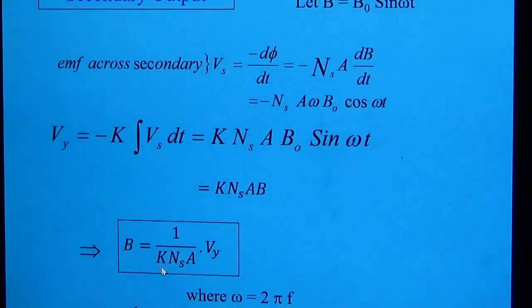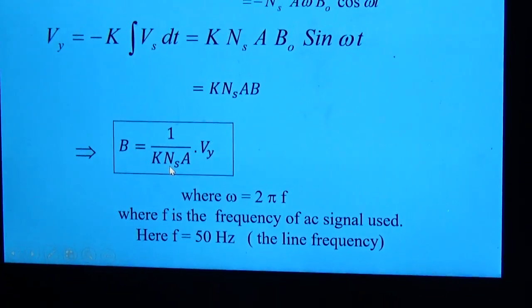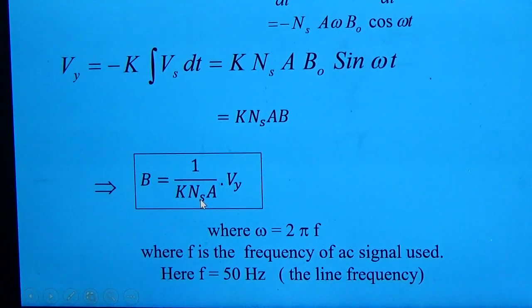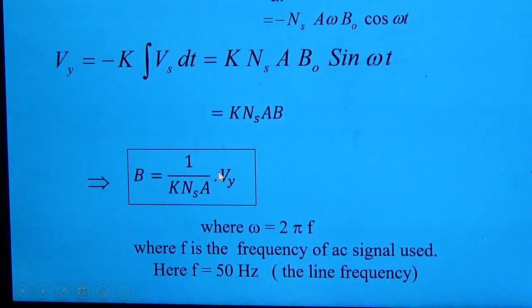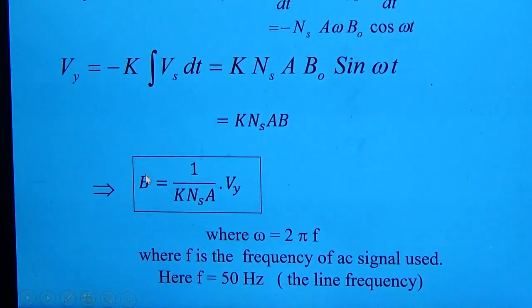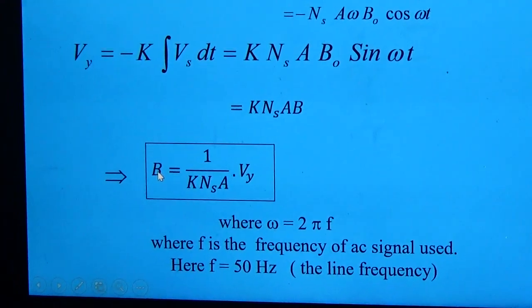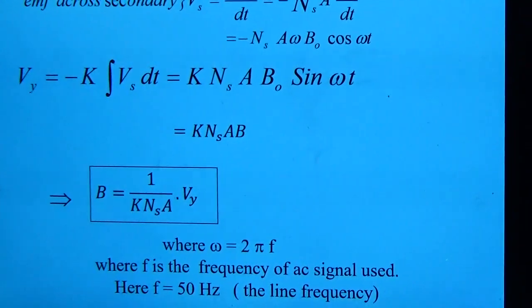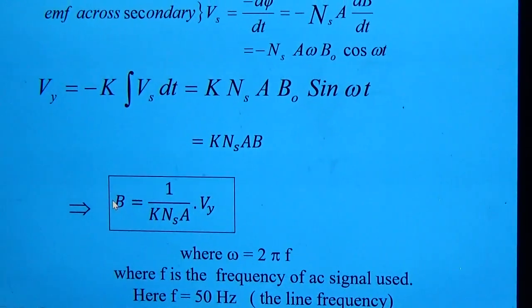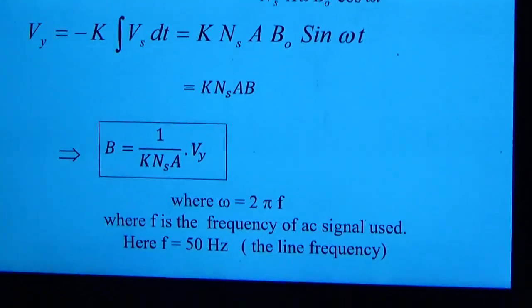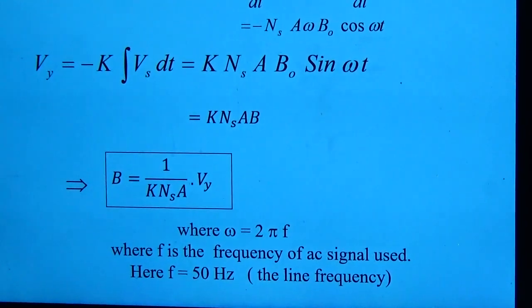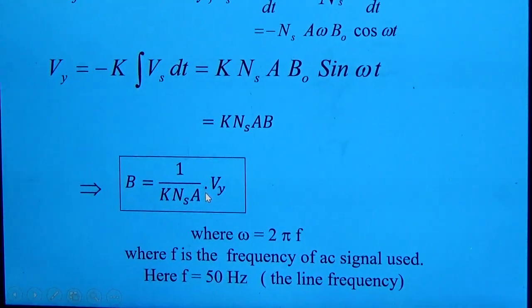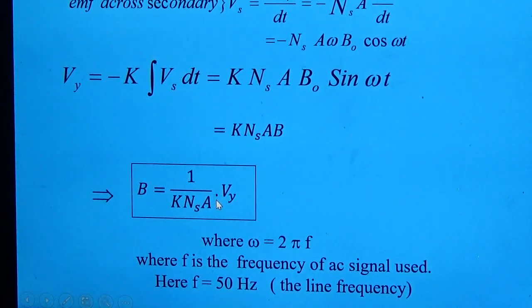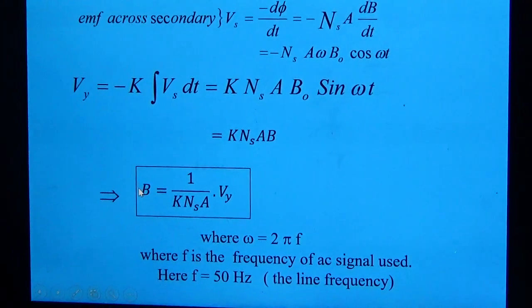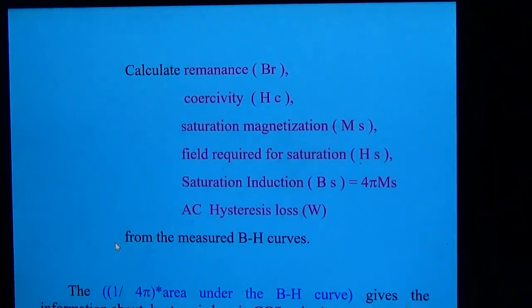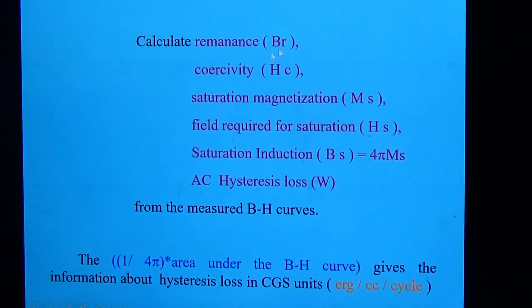So if you know the calibration constant and you know the number of turns and you know the area of the coil, and you can measure Vy from the oscilloscope, so I can actually calculate the magnetic induction for a given material. And if I measure this B at the saturation, I will get the saturation magnetic field, and if I measure B, that is Vy, at x equal to 0, or when the field is 0, then I get the corresponding remanent magnetization. So from this I can measure Br.